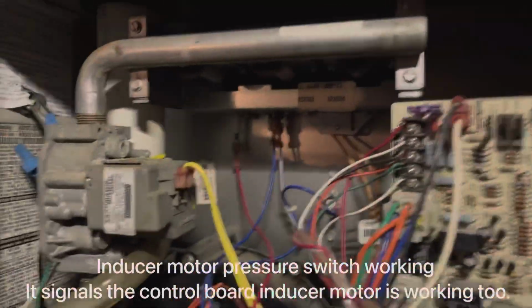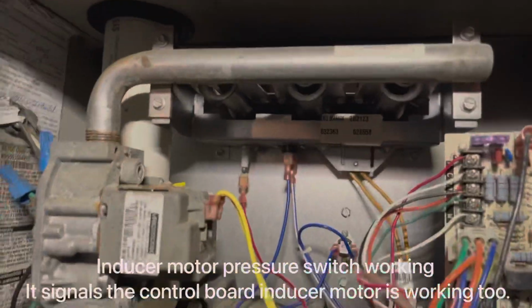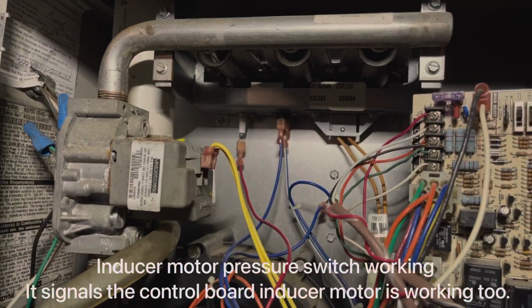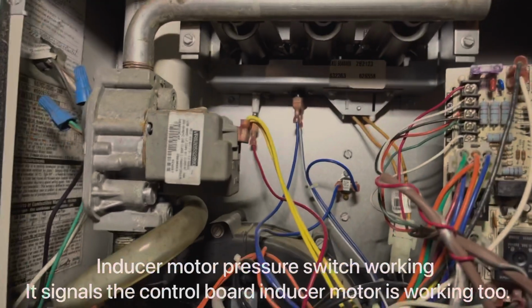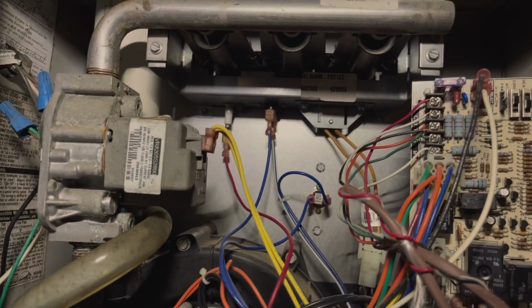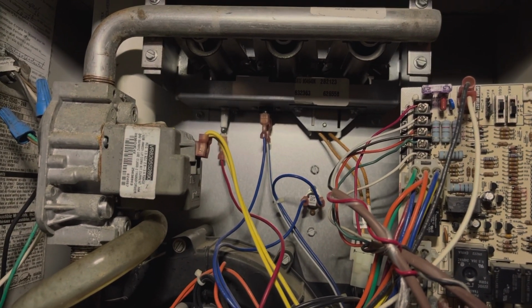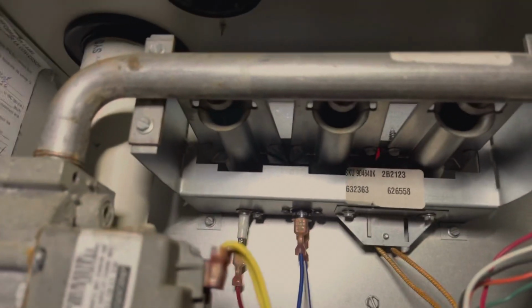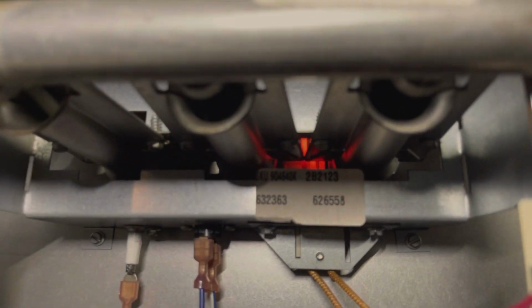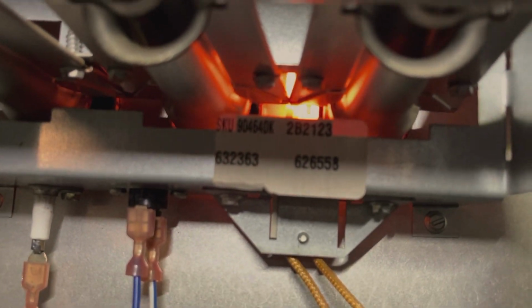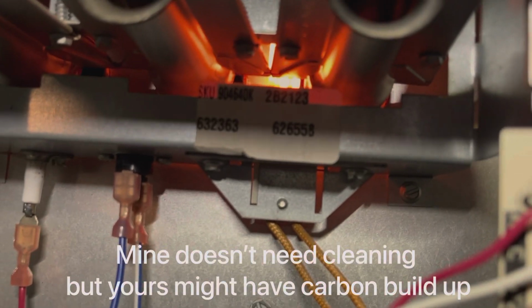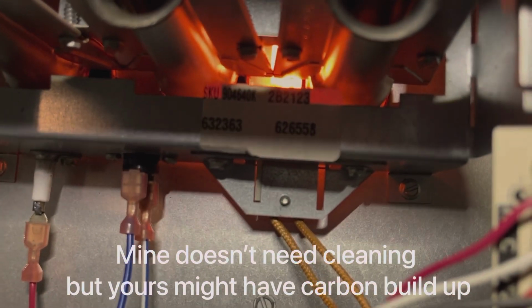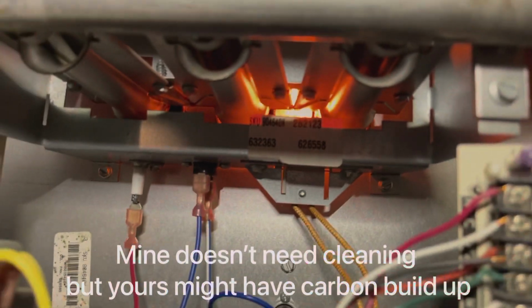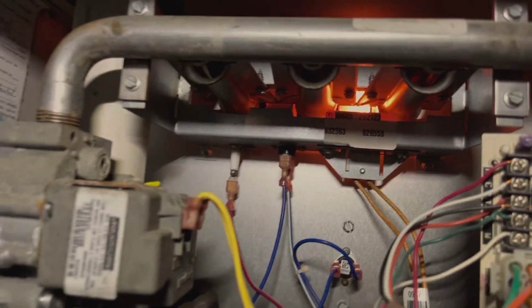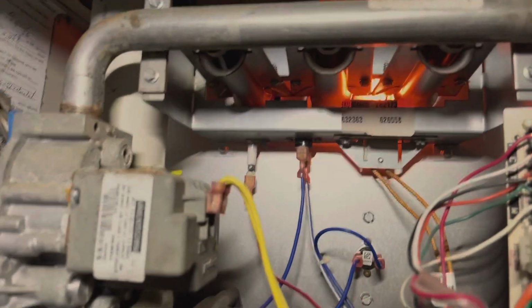Well, not necessarily, because they can trip in the sequence, but they're working, they're not stuck open or closed. They could trip because something else is the issue or whatever. So I just heard something else click. Now see that glowing? There's your igniter glowing. Like I mentioned, 2 wires, 2 screws right there you can see. You can pull that out. I don't think that really needs to get cleaned, but it could use a cleaning or replacing if that's not working. Now that's glowing now.